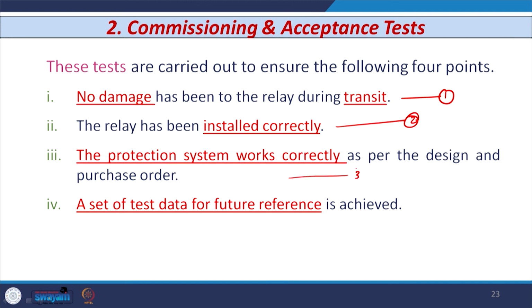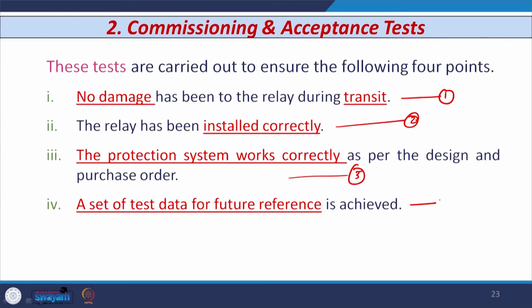The third thing that is very important is that the protection system works correctly as per the design and the purchase order. Whatever design parameters I have mentioned in the purchase order, the manufacturer has to manufacture the relay accordingly, and the relay has to pass all the type tests. Then, whenever I receive it, I need to ensure that the relay I am purchasing from the manufacturer is installed correctly and performs correctly as per the design and the various parameters mentioned in the purchase order.